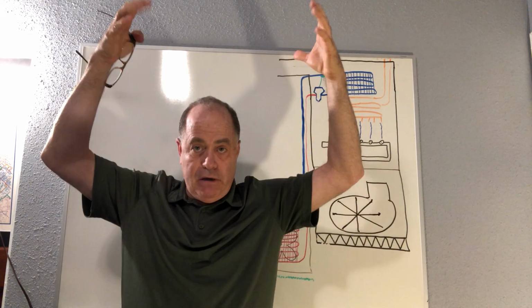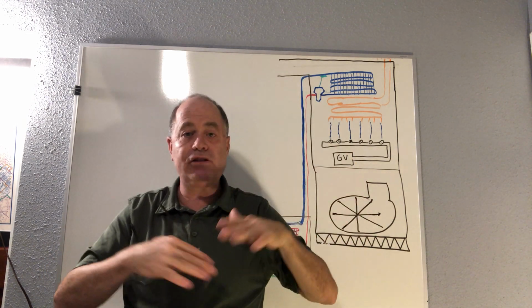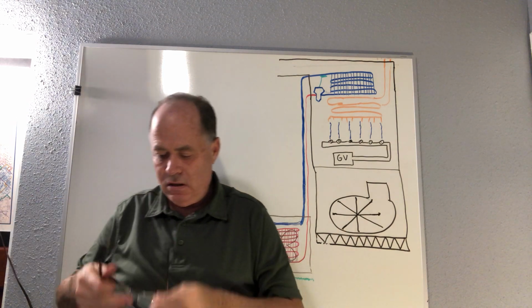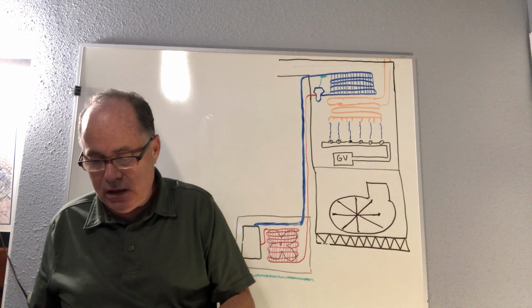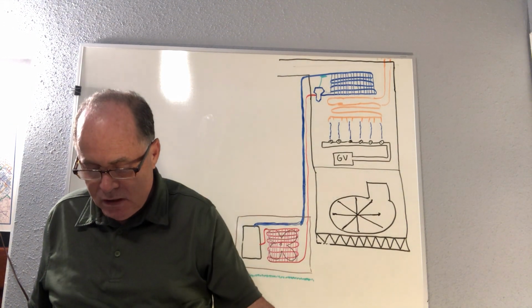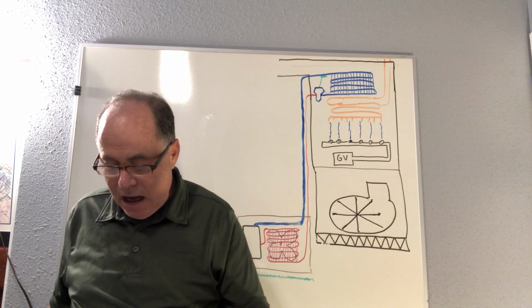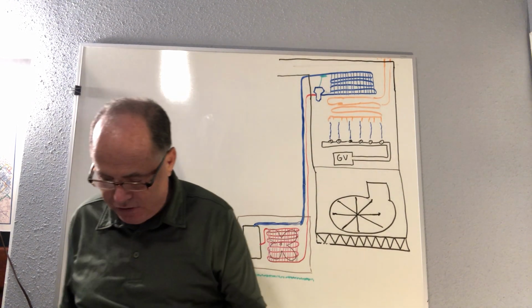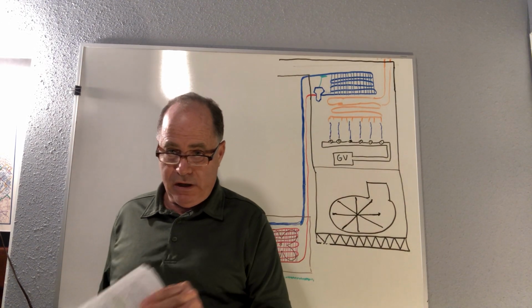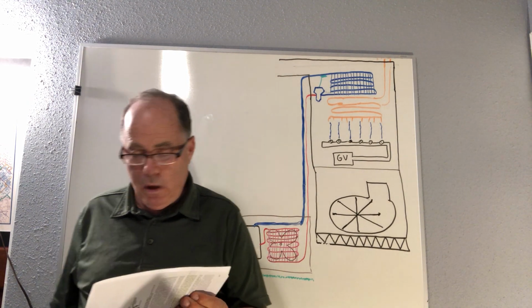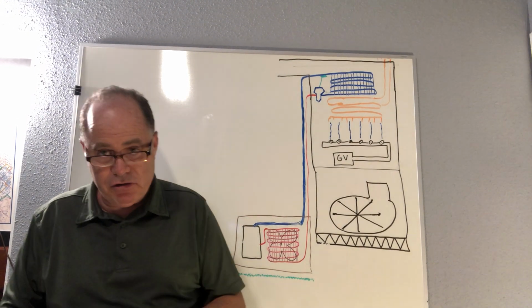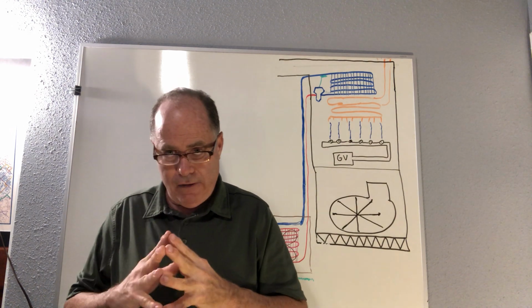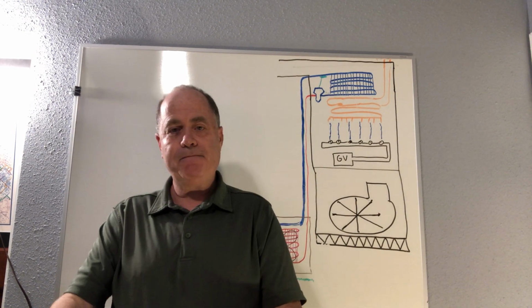And again, anything that's supported from above, like hanging on all thread or threaded rod, you have to have 6 inches of clearance off the ground. That means nothing would be underneath it, though. Okay, and then finally we conclude the unit where it talks a little bit about high efficiency particulate air filters shall be installed according to the manufacturer's instructions. What is the abbreviation for that? A HEPA filter. Okay, those are some interesting points for installation of specific appliances. Thank you.